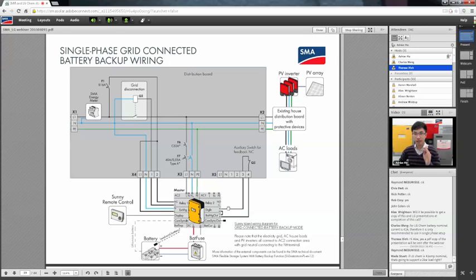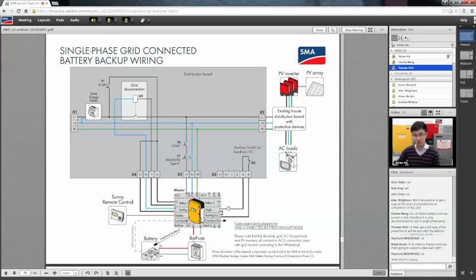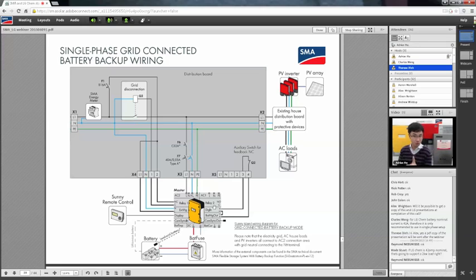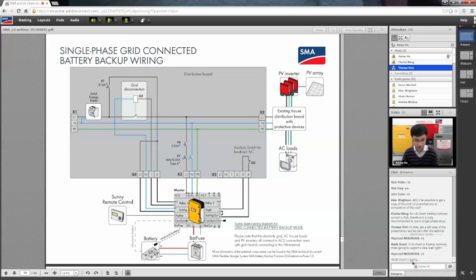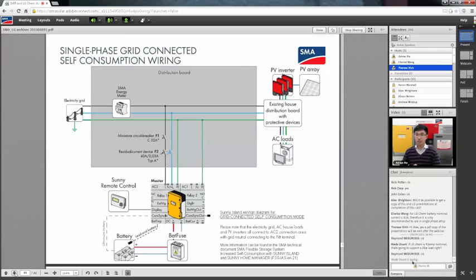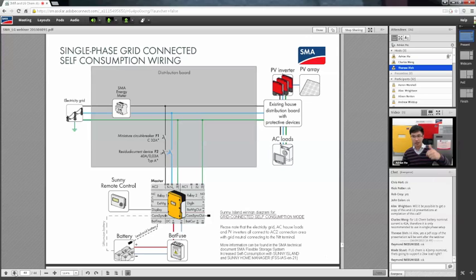Is everything okay so far with the battery backup wiring? There's a backup function here, so you need the Q2 and auxiliary switches and some other RCD stuff. If the customer purely wants self-consumption, you don't need that much extra work—this applies only to scenario 1 and scenario 2. You don't need the Q2 stuff at all. Basically, it's just putting the Sunny Island and battery in the shed, supplying the home. The energy meter and home manager are still required because they need to measure consumption to tell the Sunny Island to discharge the battery.